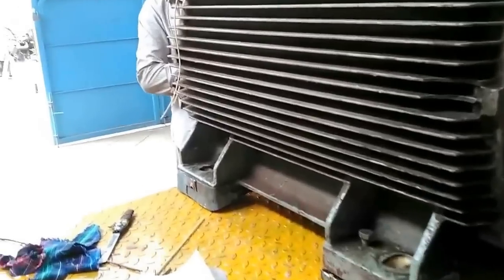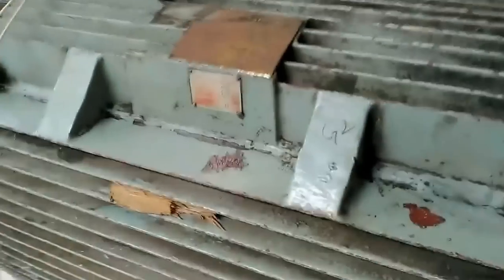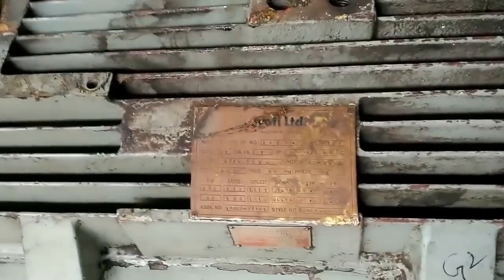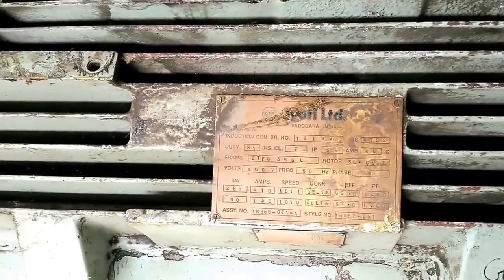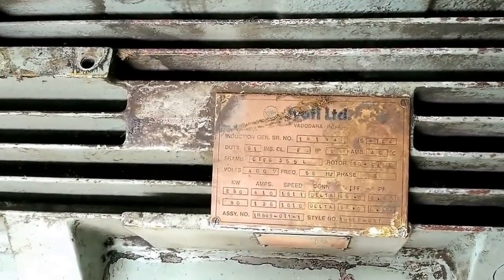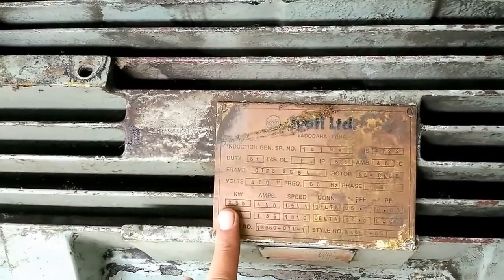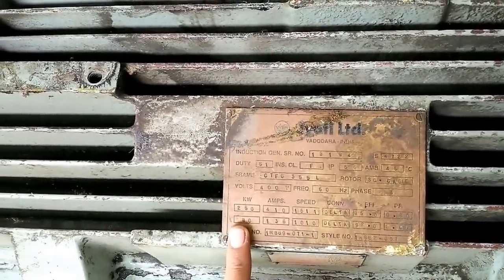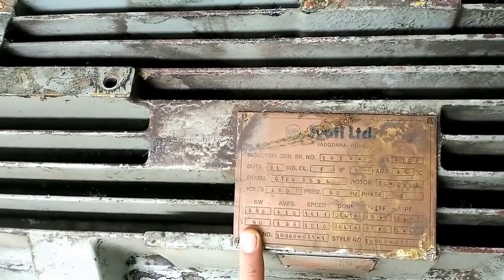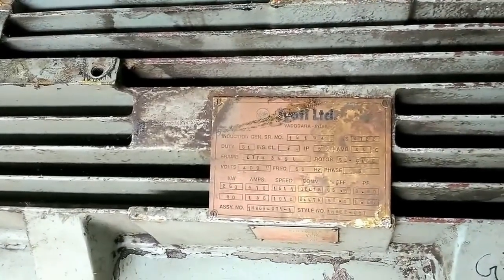Yeah, from day one I have not captured the nameplate details. Let me pull that. This is the nameplate detail of it. So you can see it's Jyothi Limited. And as I said, you have a lower winding, which is 250 kilowatt, and upper winding, which is 80 kilowatt. Both put across, they're close to 500 HP motor.